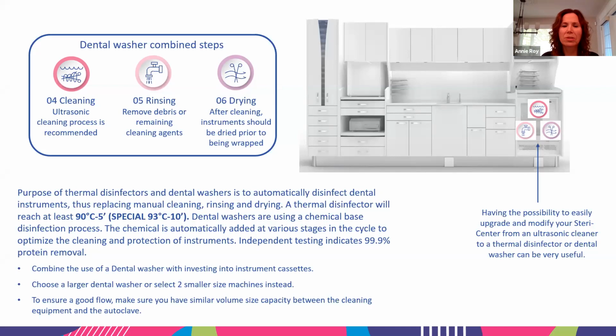And what's the typical cycle time of a dental washer? Yeah, a typical cycle time for a washer is going to be about 40 minutes. Can be a little bit faster, or if you have complicated loads and you do this as a matter of routine, you can actually increase the drying time. Particular one that I'm very familiar with, it's going to have about a half-hour wash time, about a 10-minute dry time. So that brings us out to the 40 minutes.